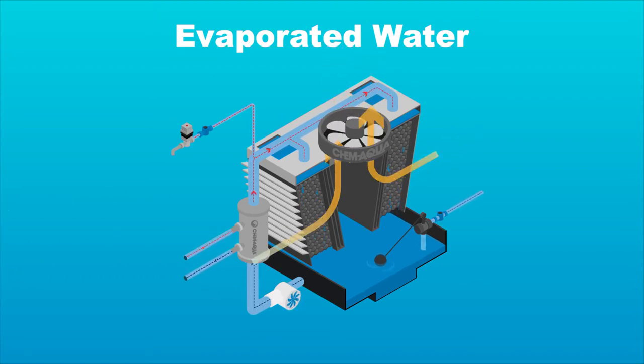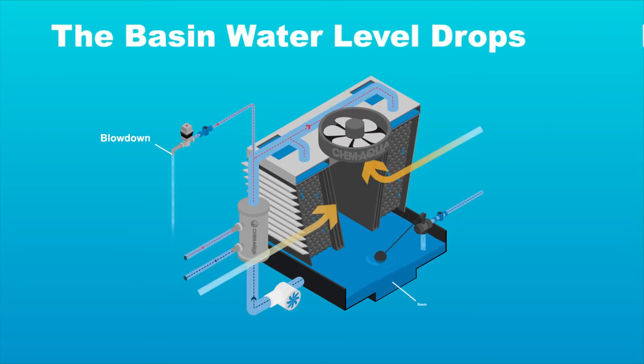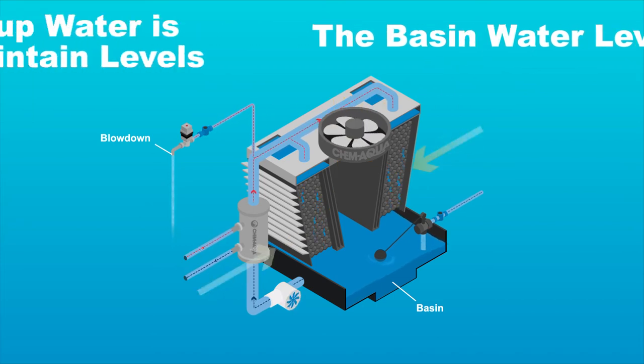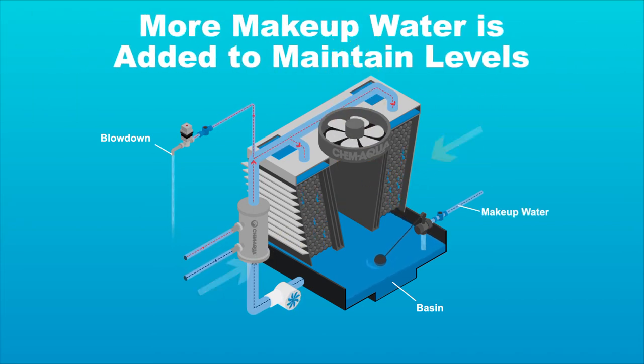Concentrated impurities in the tower water are removed through blowing down a fraction of system water to the drain. The basin water level drops due to these evaporation and blowdown losses, and more makeup water is added to maintain the basin level.